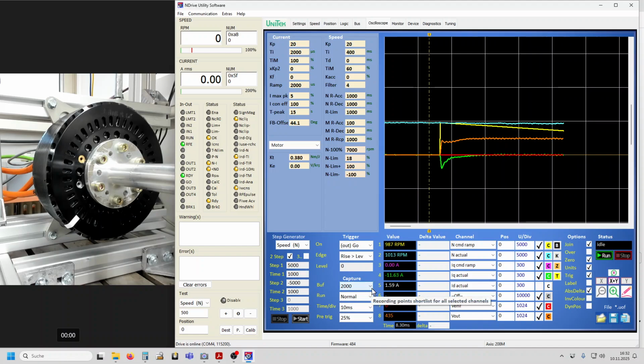For capturing, I recommend 2000 buffering points, a normal run operation, meaning it will do a measurement each time the trigger level has been activated. And for the time per division, I recommend 10 milliseconds because we want to have a close view just after the enable. And I recommend to use a pre-trigger of 25% so that the enable process will be centered a bit more and we can see more.